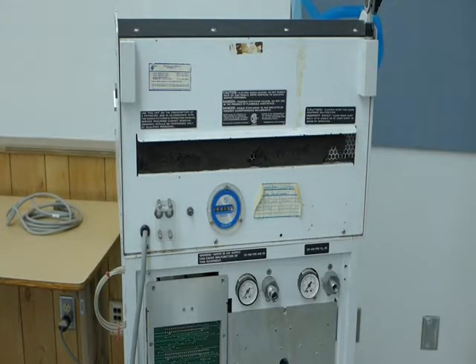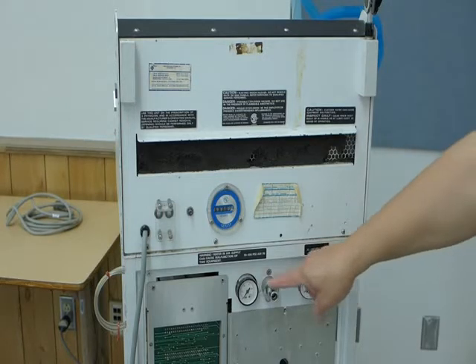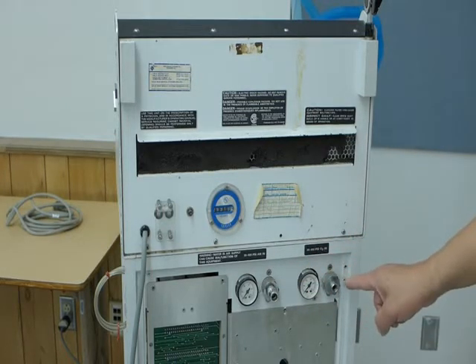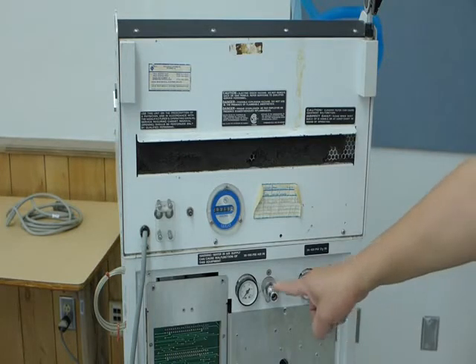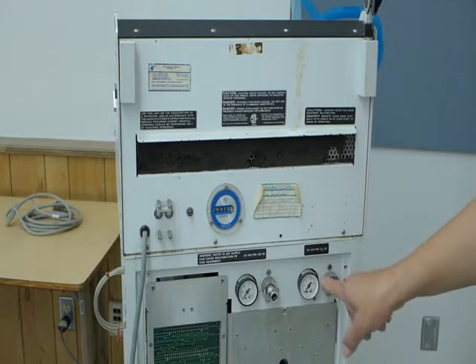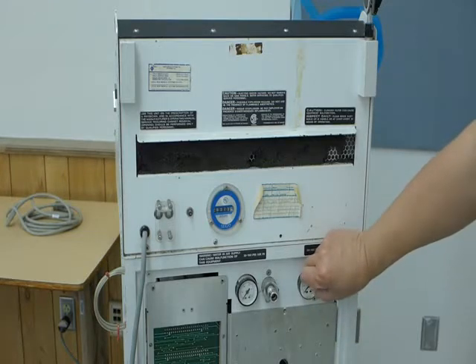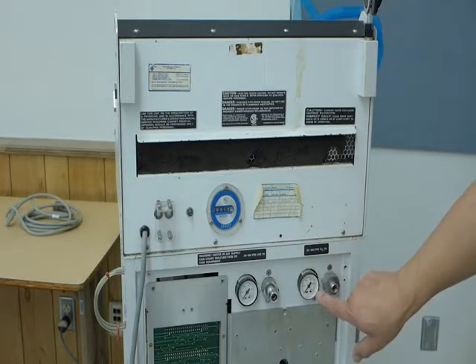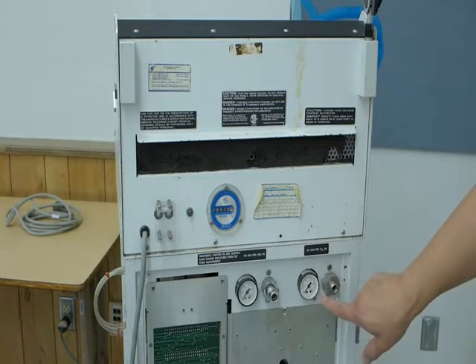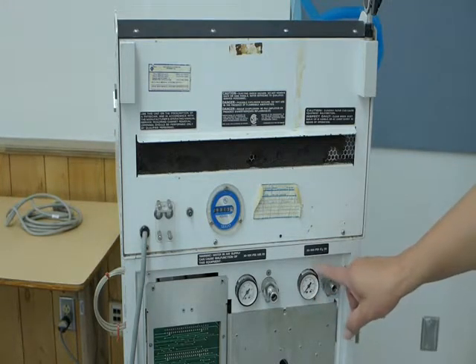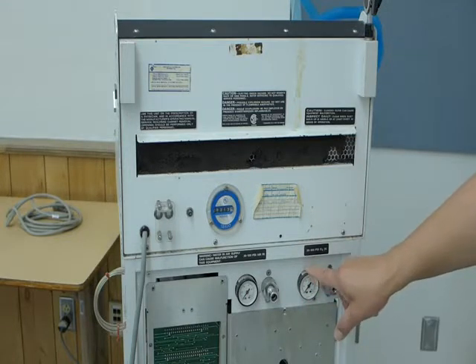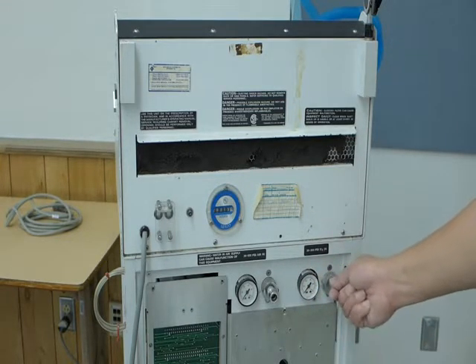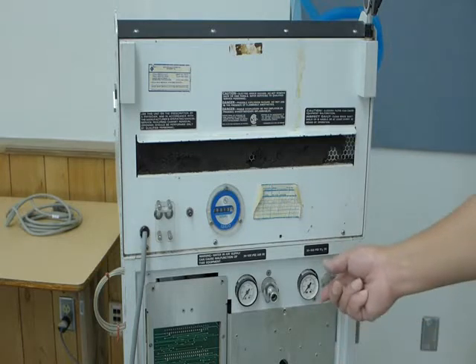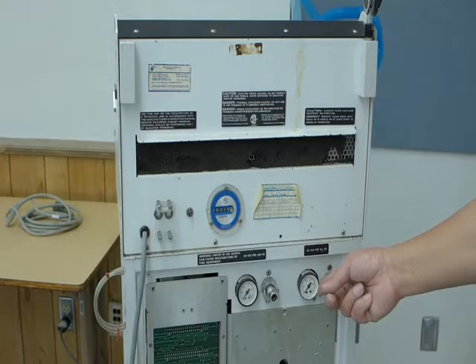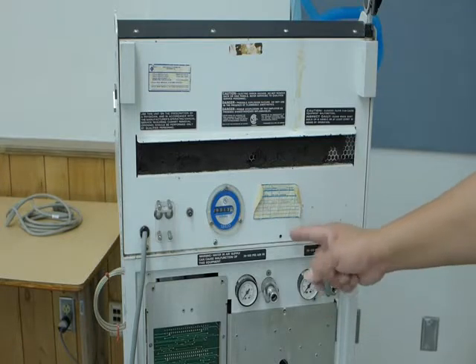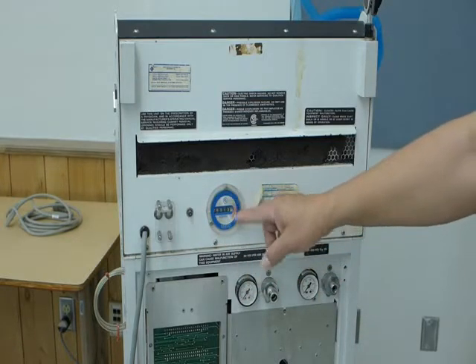On the back of the machine here, it's got two gas inlets. One is oxygen, one is air, okay? And it's got pressure regulators. Actually, it's a small regulator inside of the check valve, and also this is the pressure gauge. The pressure gauge is detecting how much pressure is coming in from the hospital pipeline, right? And also this one has the hour meter, showing how many hours have been used.